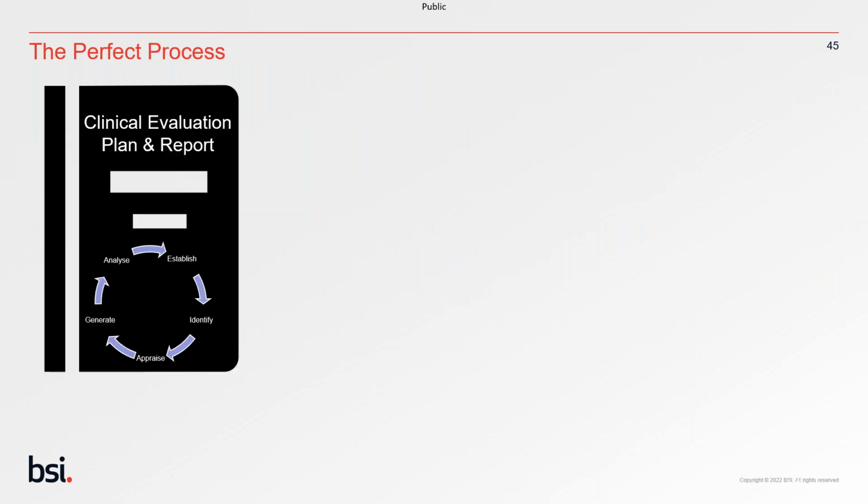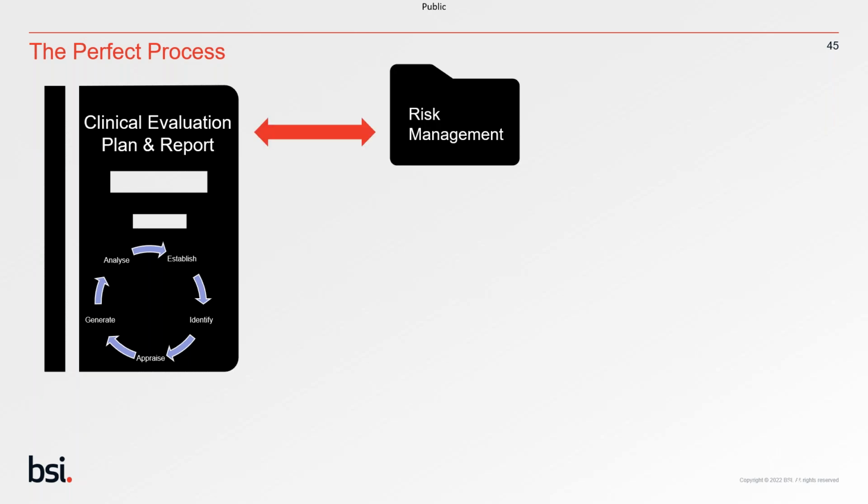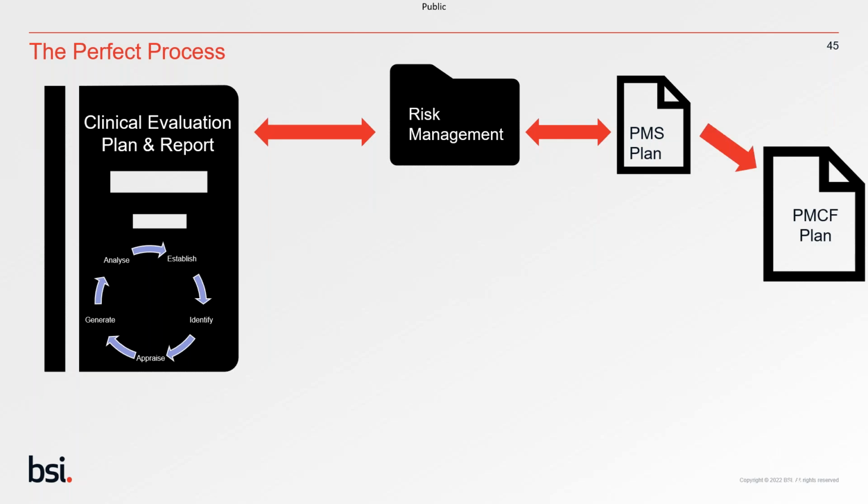And here I've got a slide that talks about this, in terms of what we're expecting and the processes to think about. So the first one is really thinking about that there is an interconnection and a continuous connection between your clinical evaluation and risk management. So whatever data you're deriving for your clinical data will need to feed into your risk management. And it's the output of that as well that you might define what activities you need to conduct as part of your post-market surveillance plan.